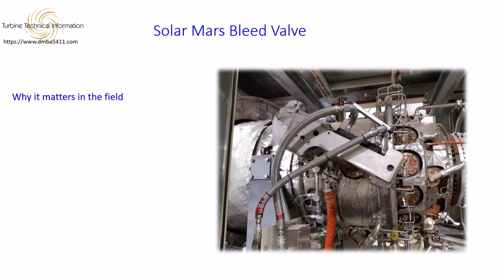Why it matters in the field. Here's the trade-off. Every pound of air you dump overboard is air that is not going through the turbine to make power. So yes, the bleed slows acceleration. Too much bleed and you have a hung start. Too little bleed and you have surge. That balance is the whole game. And when you're standing on the deck, watching a unit struggling to accelerate, this valve is one of the first suspects, because it directly controls compressor stability during the most vulnerable part of the start sequence.